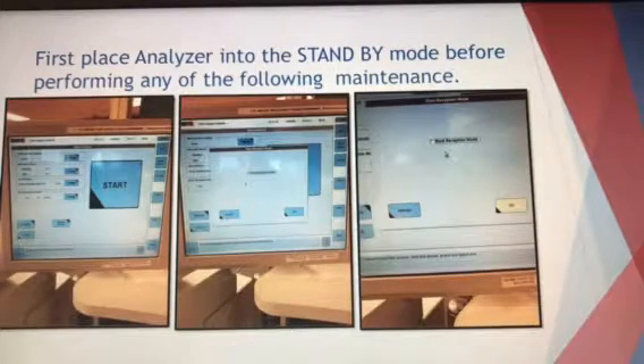So the first thing we're going to do is make sure the analyzer is in the standby mode before we do any of the maintenance. Now, standby is something that we've all become really familiar with, especially if anything is wrong with it. If you need to reset it or do anything with the instrument, the first thing we do is put it into standby. So when we're doing our maintenance, that is also the first thing that we're going to do. So how we do that is we press that big start button.